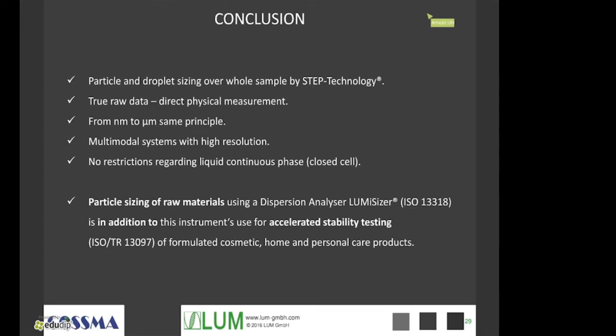We can determine multi-modality and characterize particle size and droplet size distributions of multimodal systems with very high resolution. This is based on the fact that we are using a separating technique. We also have absolutely no restrictions regarding liquid continuous phases, because we put every sample in its own closed cell. So if you would like to compare titanium dioxide in water with titanium dioxide dispersed in oil, it is the same measurement, the same run in the same instrument.